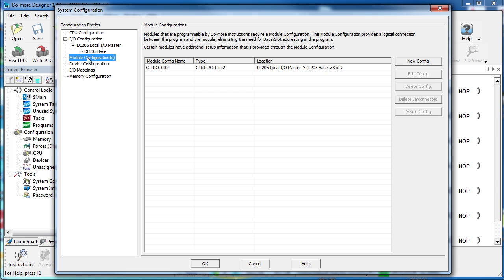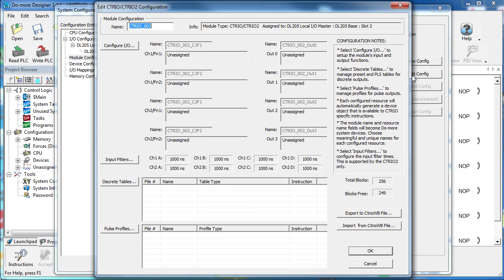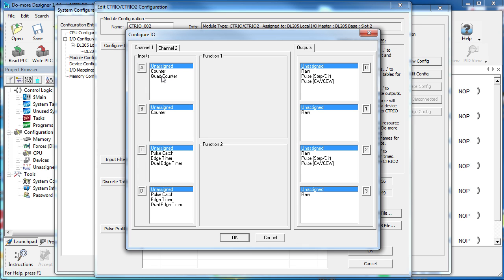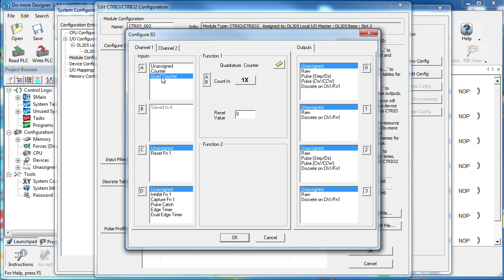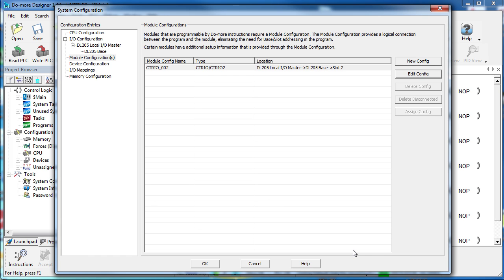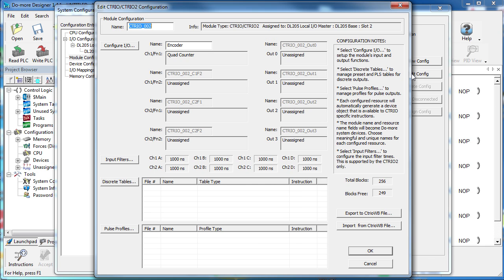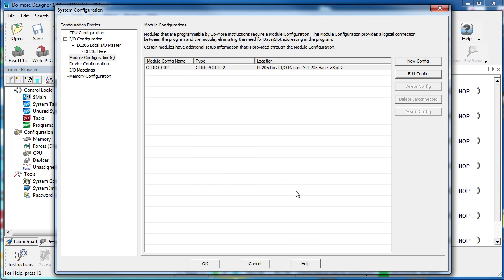Here is a list of all of the configurable modules, which we only have one. Select it, click on Edit and Configure I/O. We want a Quad Counter so we can tell which direction the encoder is rotating and let's call this device Encoder. Hit OK and now we have a fully configured encoder device. Again, all we did was go into the module configurations, select the CTRIO module and create a Quad Counter device which we named Encoder. We didn't have to do anything special to initialize the CTRIO module. It only took us a couple seconds to fully configure our encoder device.